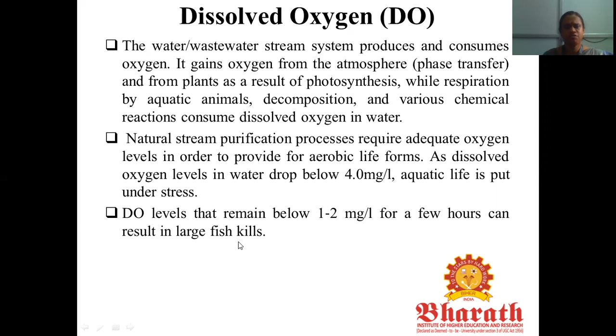So usually DO is measured using DO meters and probes. We have electrochemical DO sensors as well as optical sensors available in the market. These meters and probes measure temperature and give standard analog outputs as well as digital outputs in the form of smart sensor platforms. These probes and meters should be calibrated from time to time to get accurate measurements.